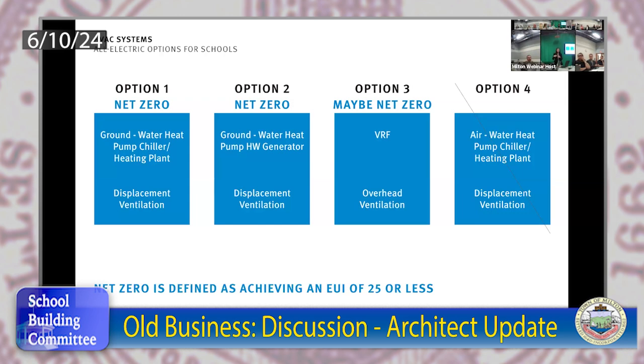And then that is running to your air handling units, that's running to radiant cooling in your spaces. Where option 2 is only doing the heating side of that. And then on the cooling side, it basically removes chilled water from your building. And so because you don't have that chilled water, you can't get to that full cooling level. So you can do the dehumidification. We would do dehumidification in everything because humidity is actually a lot of the component of cooling, being able to dehumidify that air.